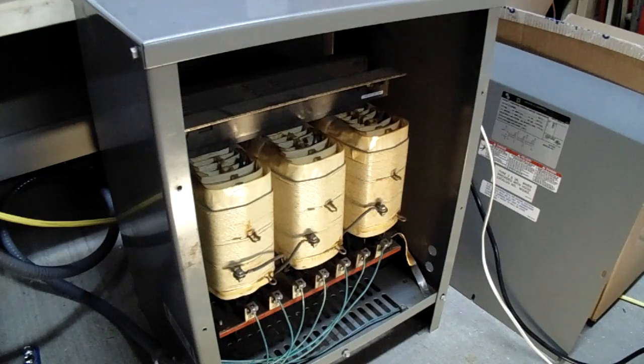So in the delta configuration, the output of the phase converter is so imbalanced that if I try to put that voltage into the transformer it flips out and doesn't like it because it wants a balanced voltage, where on the rotary phase converter I might have 230 volts on one leg, 230 volts on the other, and then on the generated leg I might have 215 or I might have 260, and that's a very large imbalance for the transformer, and it does not like that. So today I'm going to convert this transformer to a star-star configuration.